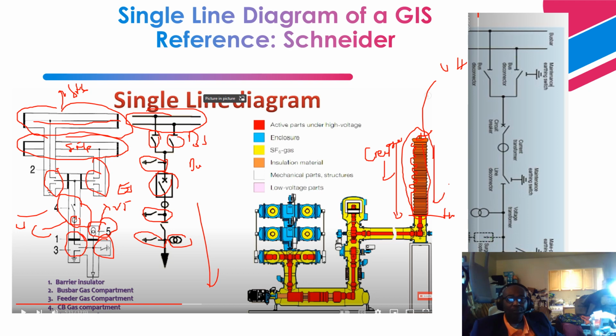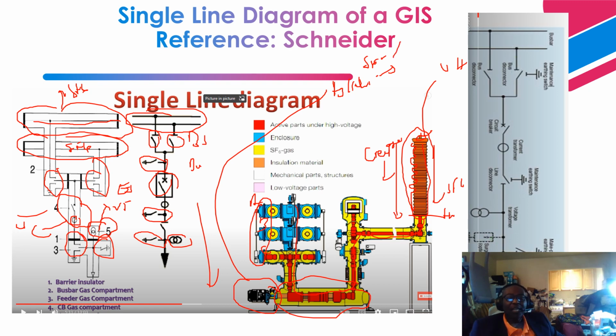All this is filled with SF6 gas, right? And within this enclosure, all of them is filled with SF6 gas, right? Okay, so these are basically the disconnect switches, right, for each phase. Phase A, phase B, and phase C, right? This is the circuit breaker, right? And this is the operating mechanism for a circuit breaker. So the operating mechanism, you can have a hydraulic system that utilizes hydraulic oil, right? Okay, so pressurized hydraulic oil, which basically compresses a spring. So the spring is charged. That basically operates the circuit breaker, right, from the open and closed position.